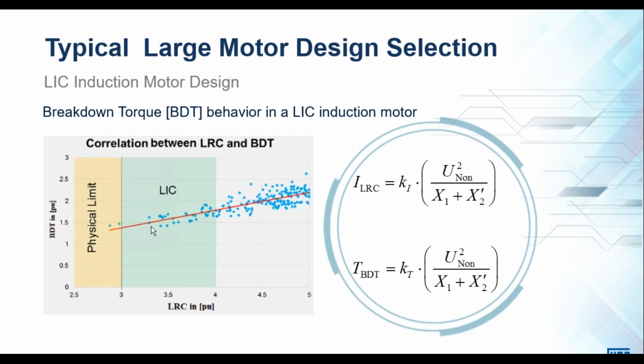And so you'll see on this graph here, what we did was we took a number of different motors that we have manufactured over the years, and we plotted them to determine the relationship between these two parameters. There is some spreading because there are some design considerations in these constants, Ki and Kt, that can make improvements between the locked rotor current and the breakdown torque. These include things like playing around with the magnetic core dimensions, the stator and rotor slot combinations and shapes, as well as the number of winding turns. However, these only have a small effect on this relationship. By far the largest effect is the decrease of the reactance of the stator and the rotor.